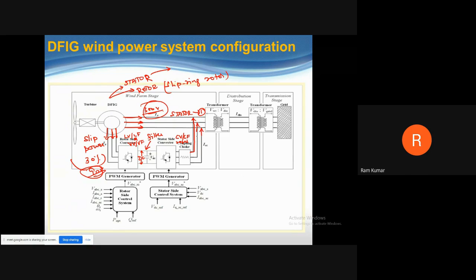Rated, and it is fed to the stator side. So the two powers are fed to the grid side, then only it is called the doubly fed induction generator. So it is given to the transformer as usual.